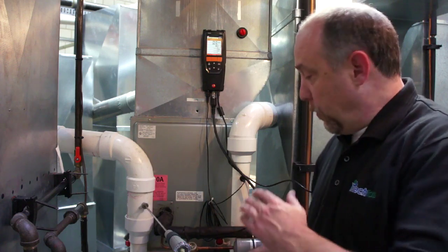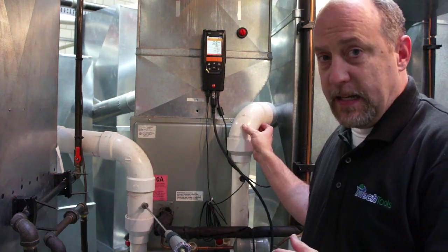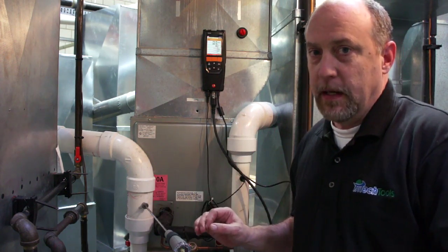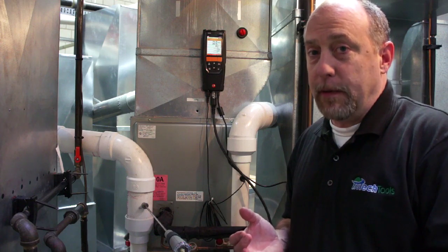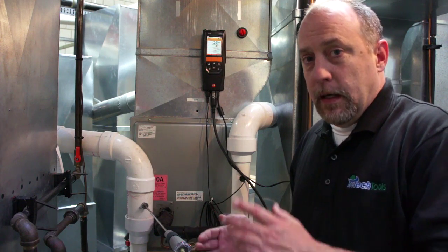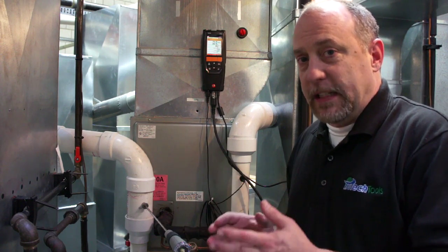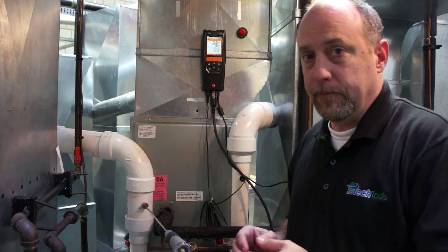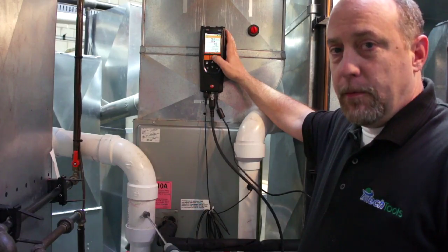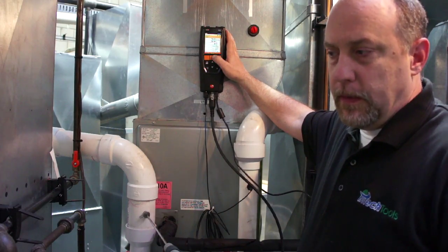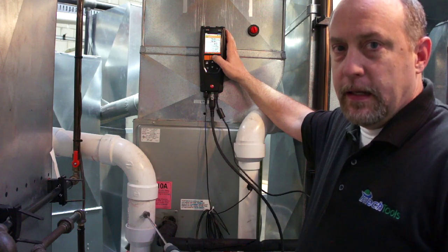We want to make sure that we're pulling air from outside through the intake pipe and not from our basement. The furnace will operate differently, or could operate differently, with that door on or off. It's designed to have the door on in operation, so that's the way we want to do the testing. The furnace has been up and running for a few seconds. It's started, the burner's lit.